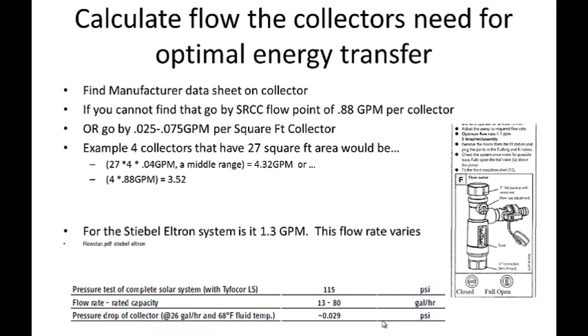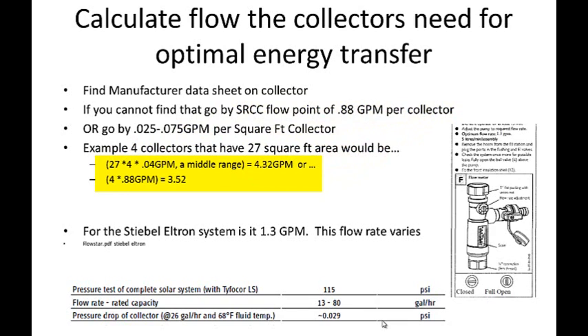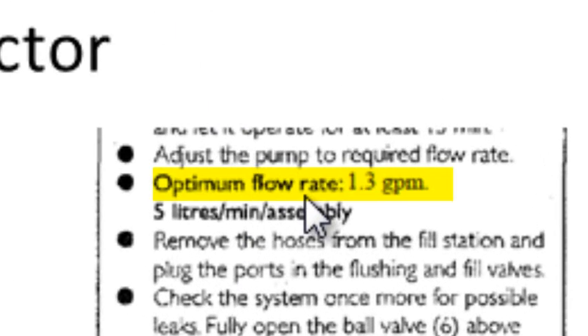Let's go to calculating the flow first. We need to know how much velocity and volume of flow to get that fluid through the collectors and back into the heat exchanger and looped again. The very first criteria is what the manufacturer data sheet states. The second thing is to determine how the SRCC flow rate compares. If I pull up the Stiebel Eltron chart from their instruction guide, utilizing their Sol 25 and Sol 27 Plus systems, they state that an optimal flow rate is going to be 1.3 gallons per minute.